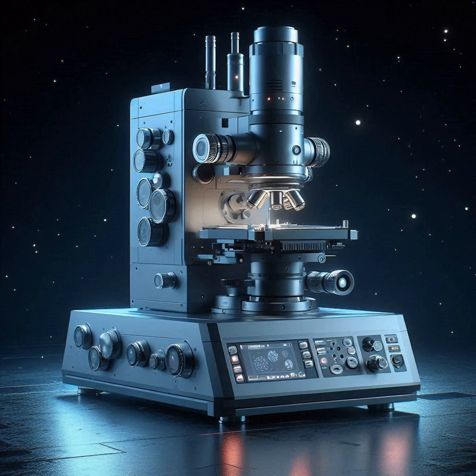Electron microscopes have a much higher resolution of about 0.1 nanometers, which compares to about 200 nanometers for light microscopes. Electron microscope may refer to transmission electron microscope, TEM, where swift electrons go through a thin sample. Scanning transmission electron microscope, STEM, which is similar to TEM with a scanned electron probe. Scanning electron microscope, SEM, which is similar to STEM but with thick samples.